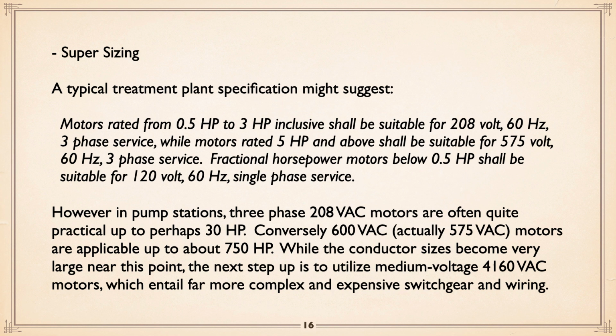However, when you get into really big stuff in pump stations, three-phase 208-volt AC motors are often quite practical up to about 30 horse. Conversely, 600 volt, which we'll see, is actually a 575-volt motor. They're assuming line losses of 25 volts, so the motors are always actually rated, in almost all cases, at something less than what the actual power service coming in is supposed to be. Applicable up to about 750 horse.